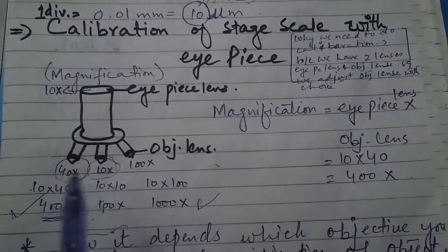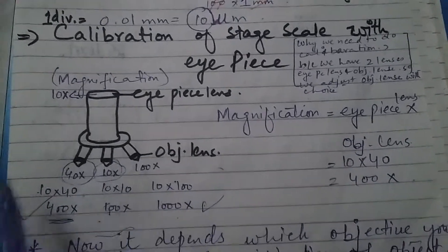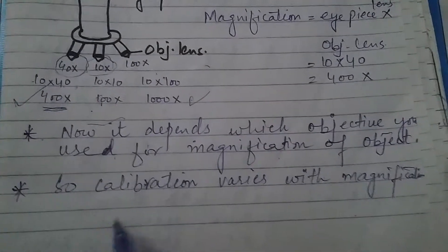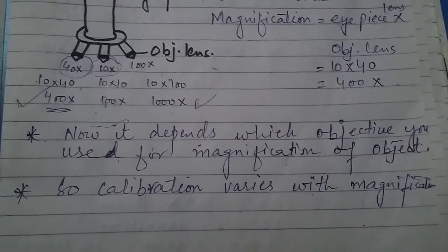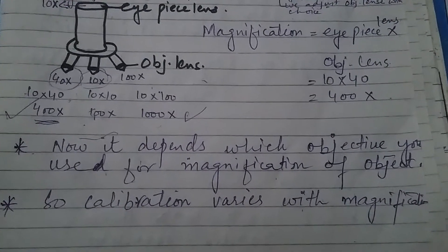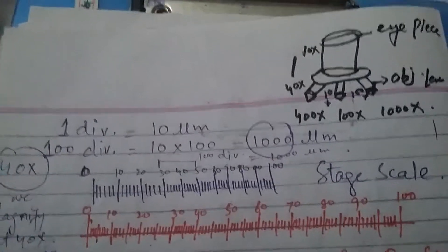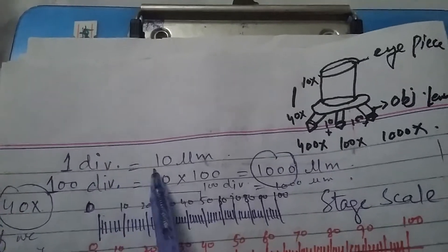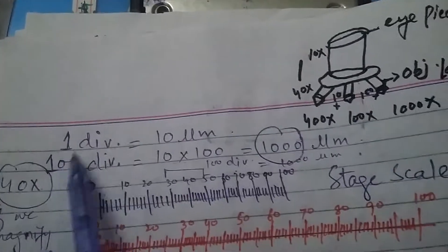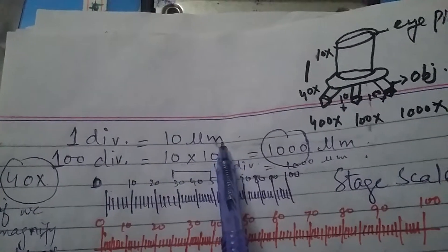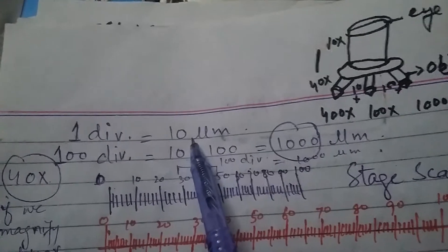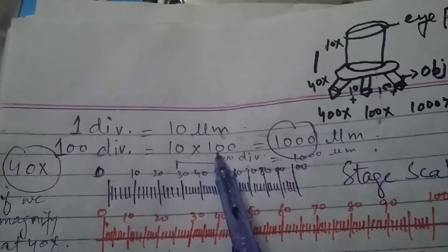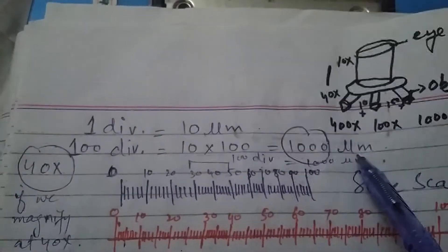Which objective lens we use determines the magnification, and calibration varies with the magnification. We established that one stage micrometer division equals 0.01 mm, which equals 10 micrometers. So 100 divisions on the stage scale equals 10 × 100 = 1000 micrometers. Therefore, 100 divisions equals 1000 micrometers.